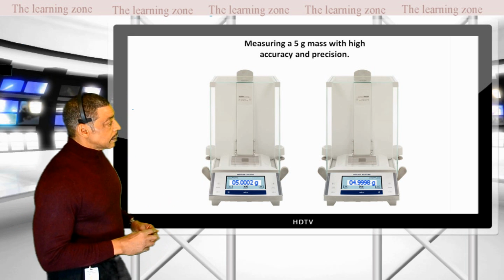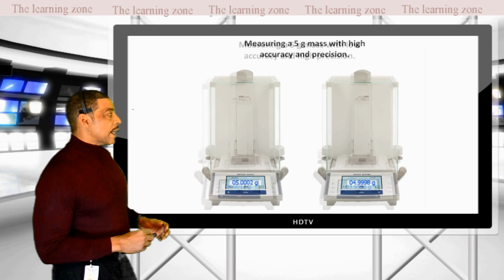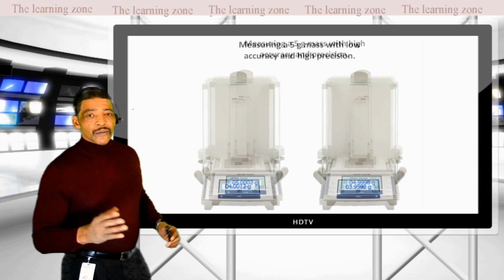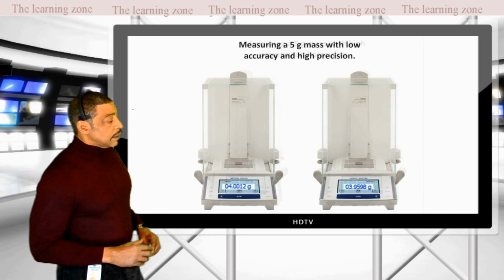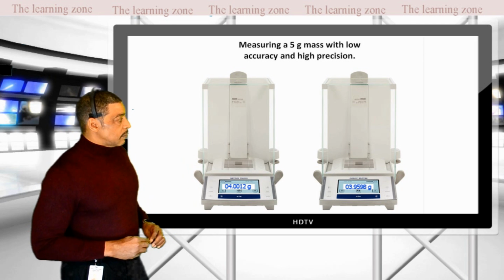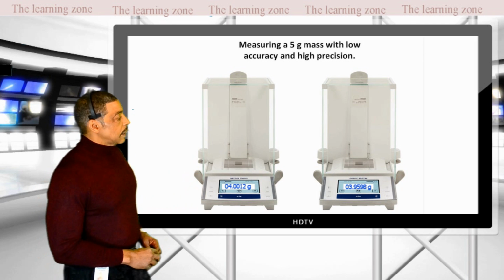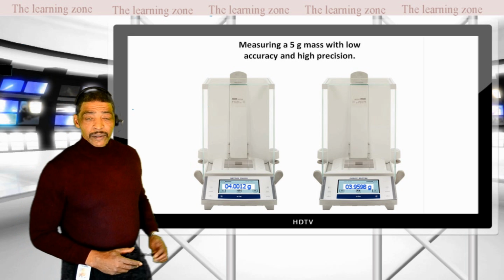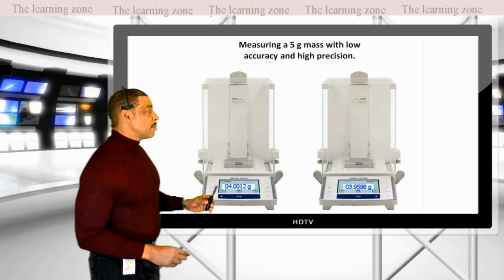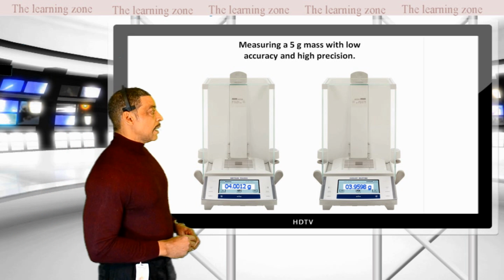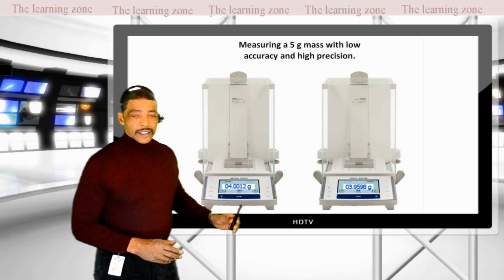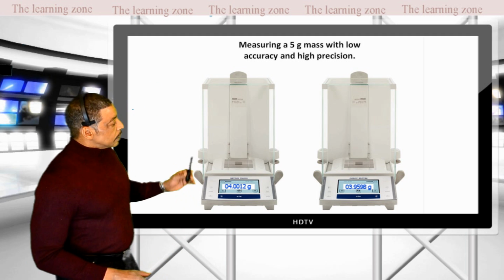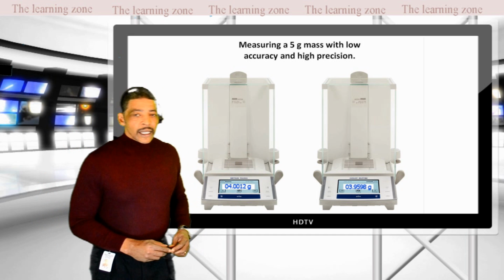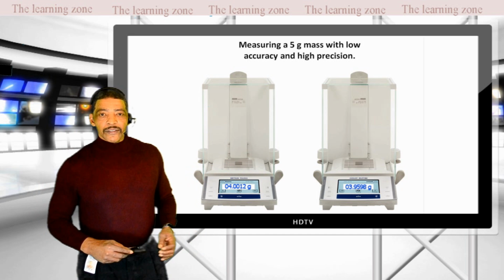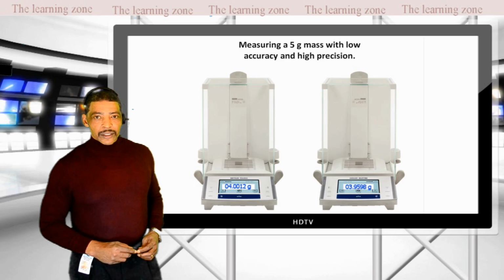On the other hand, a system showing low accuracy and high precision may yield values as follows, where the 5-gram mass is measured to be 4.0012 grams in the first case and 3.9598 grams in the second case. Clearly, in this particular case, the balance needs to undergo a process called calibration.